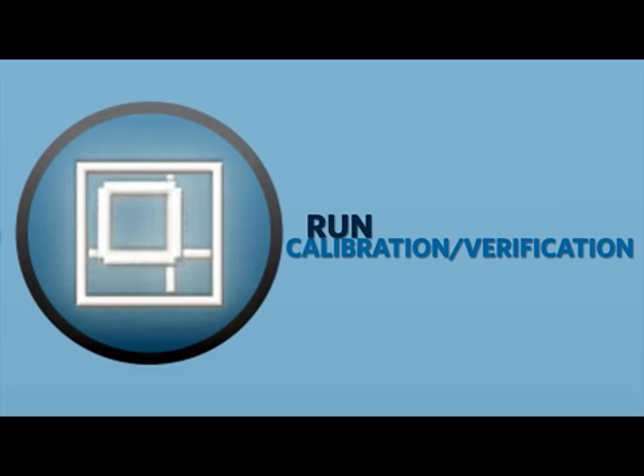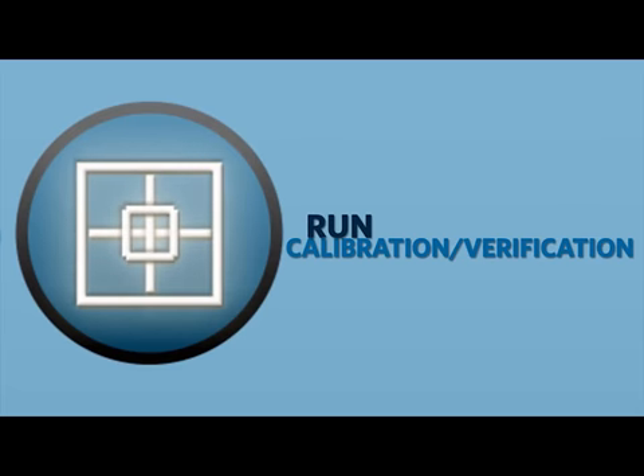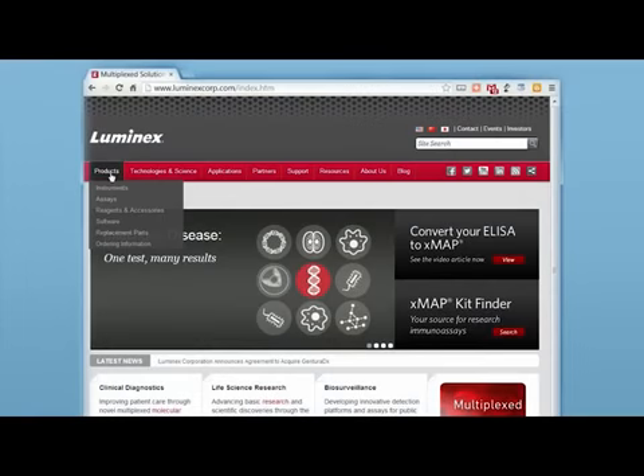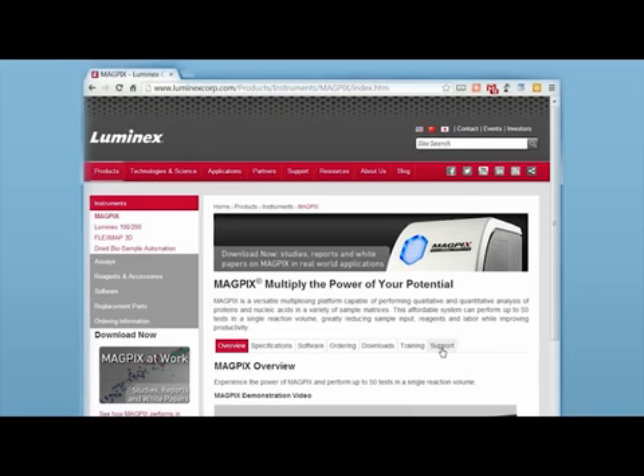The first step when getting errors on the MagPix instrument is to run a calibration and verification cycle. If you're not sure how to run the calibration and verification routine, refer to the corresponding video on the Support tab of the MagPix instrument page at www.luminexcorp.com. By completing the calibration and verification cycle, you're verifying the hardware is working properly.